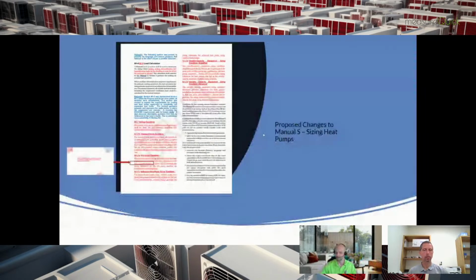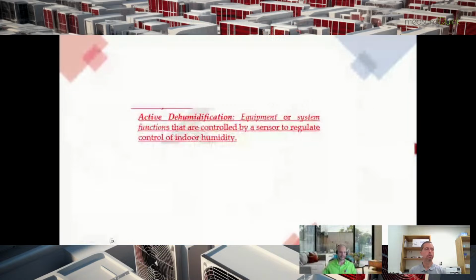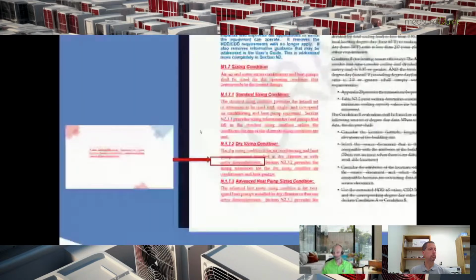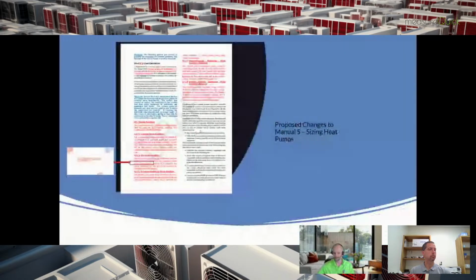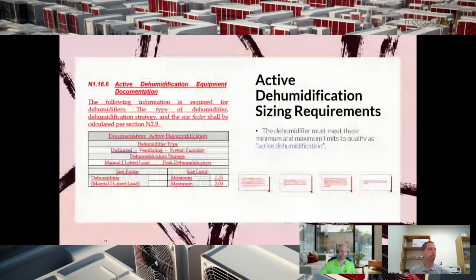And then we have one other definition that we really need to look at. It's active dehumidification. So what is active dehumidification? Equipment or system functions that are controlled by a sensor to regulate the control of indoor humidity. And you'll see that when we're talking about active dehumidification, there's actually 4 types of active dehumidification, but when we're using it in conjunction with sizing a heat pump, only 3 of these types are going to be permitted as the dehumidification strategy.